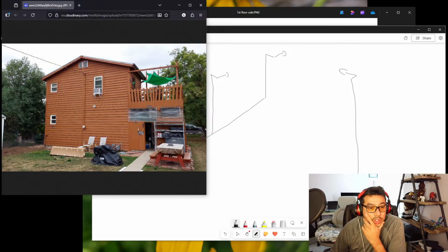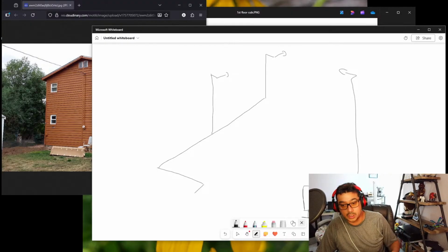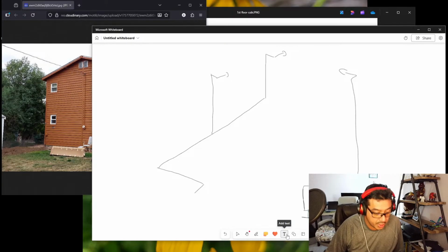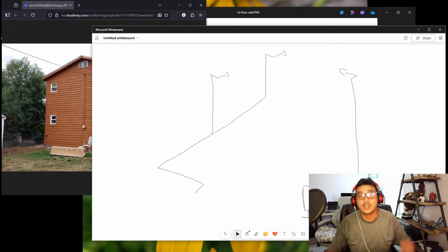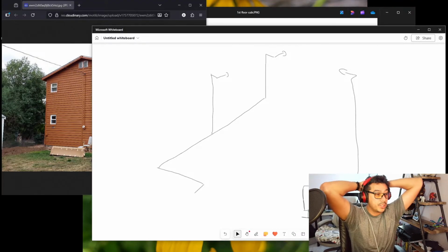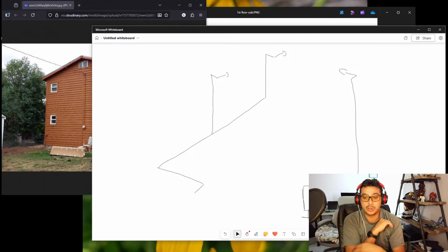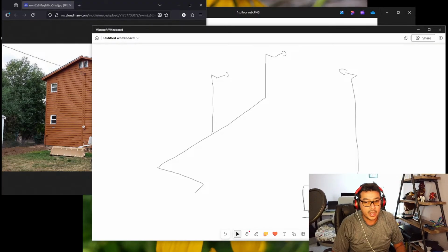So each level is 8 feet tall. So we know our condenser has its own little stand. Let's start doing some writing on our little drawing. Those stands are usually, I want to say, you can order them 12 inches off the floor or 18 inches off the floor. So in this case, I'm going to go 18 inches.